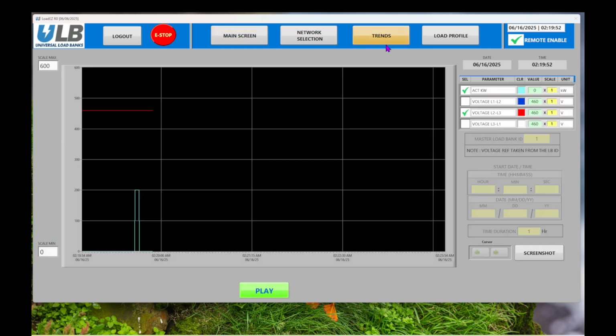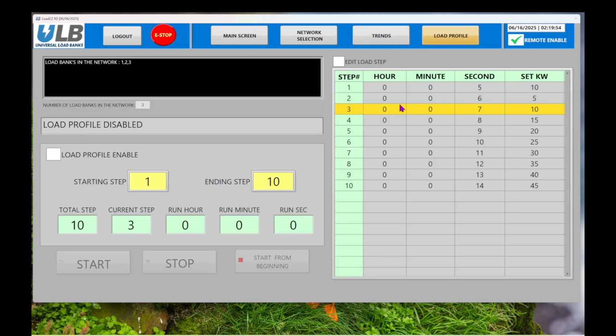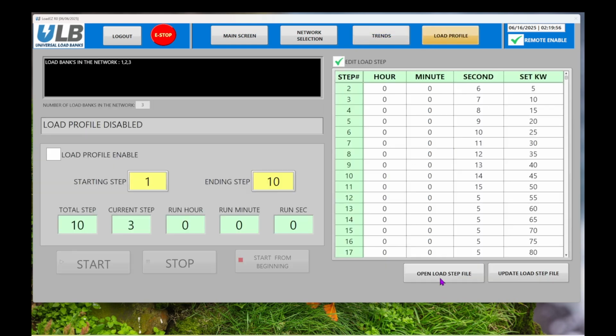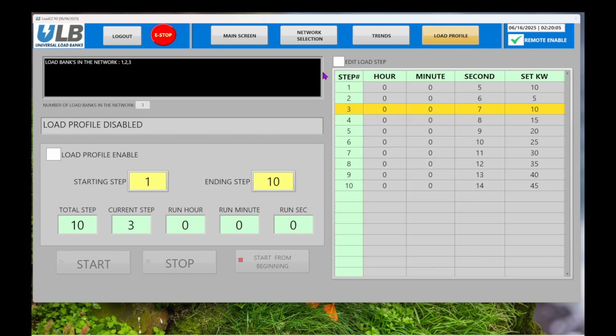To activate a load profile, press Edit Load. In each step, enter the time and kilowatt values. The values can be entered manually or uploaded from an Excel sheet. Then, enable the load profile, enter the start and end steps, and press Start. You can start or stop the profile at any time, and the system will display the current profile status.